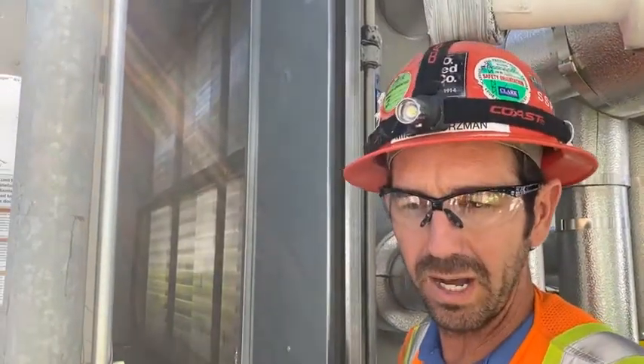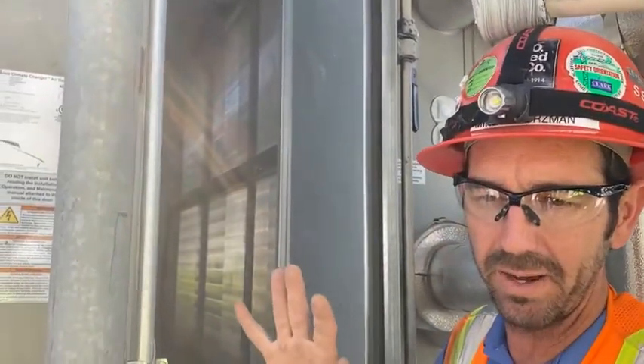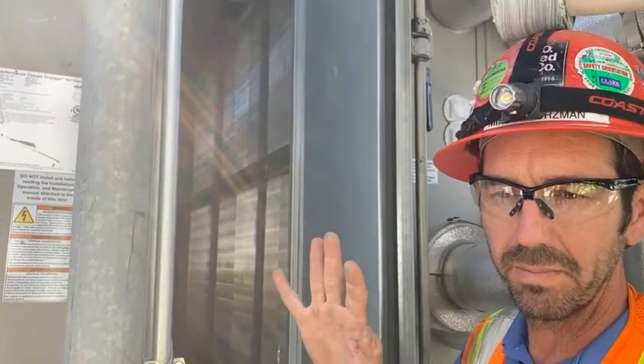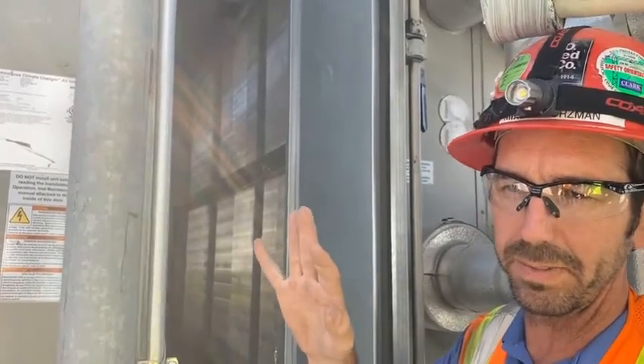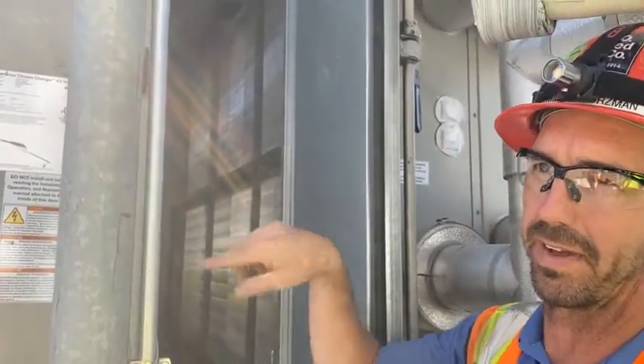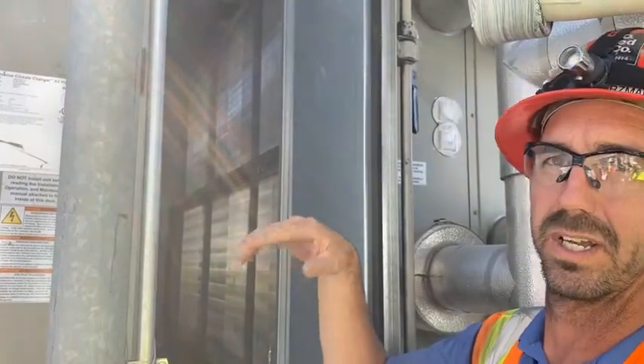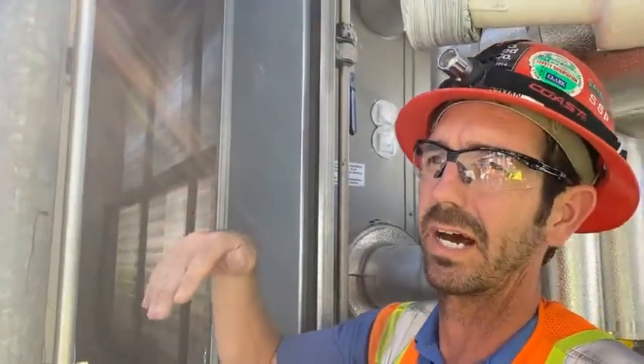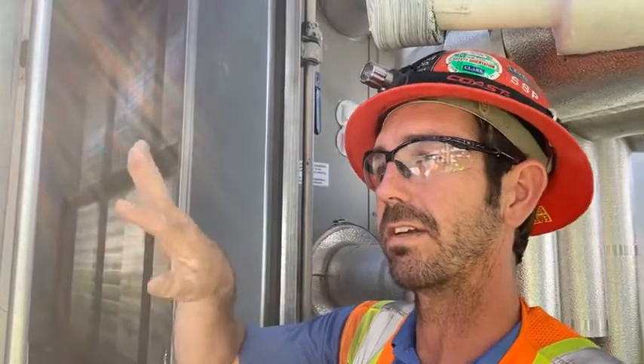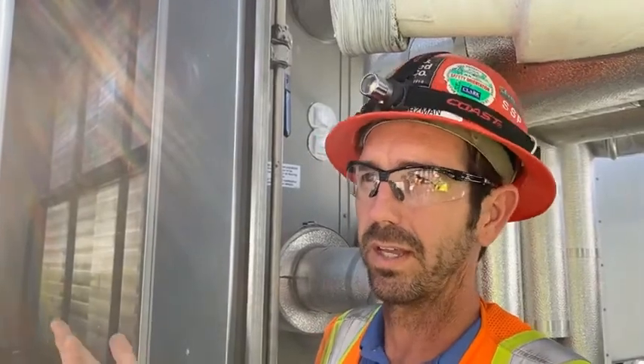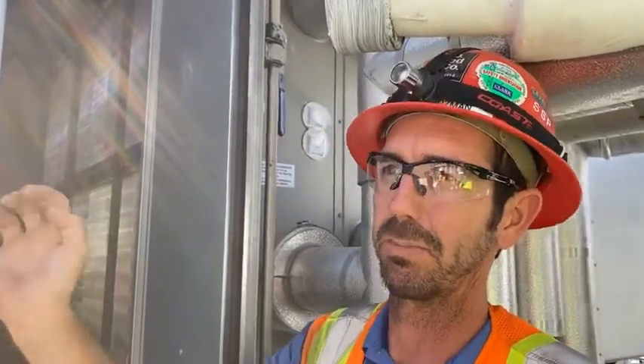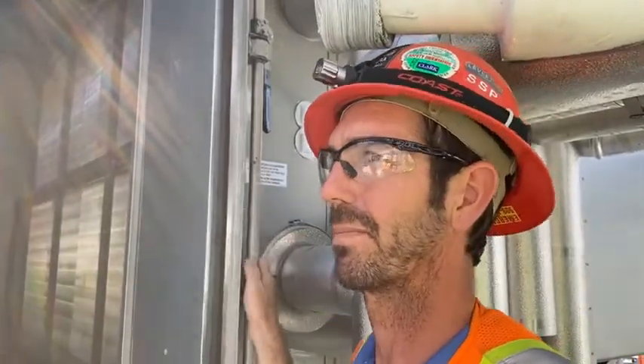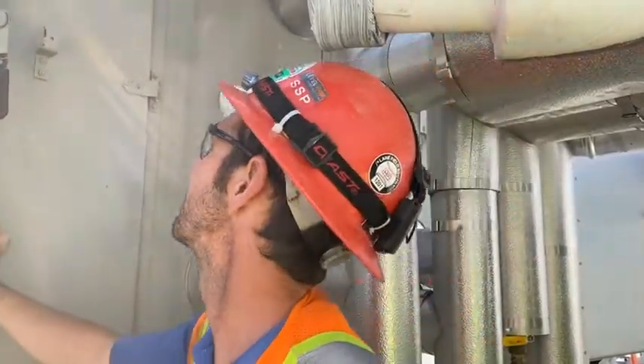This is also the inlet to the fan too. There are no inlet dampers right now. So if you lose one fan motor, potentially you could lose airflow throughout the fan. Does that make sense? It'll short cycle. There's no dampers on this unit that prevent backflow. If you lost one fan, the other one will spin backwards and you'll lose airflow. So if you lose static down in the building or lose cooling, that'd be one thing to see, make sure both fans are running at the same time. Both fans have to be running.